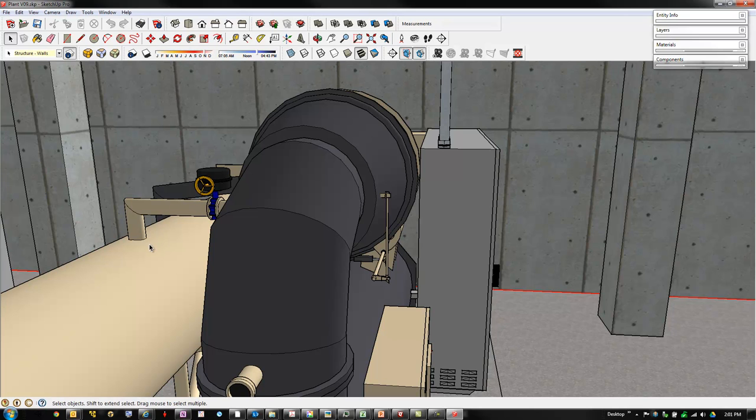And so you don't use hot gas. If you had a lot of hours where you're going to be below the minimum capacity of this machine, you'd probably actually want a chiller with lower capacity that could be much more efficient in that capacity range. But if you weren't spending a lot of hours there, or you couldn't afford the smaller machine in your project budget, at least the hot gas bypass would protect this machine from short cycling and would allow you to keep making chilled water because the loads might need it. So that's what hot gas bypass is about.